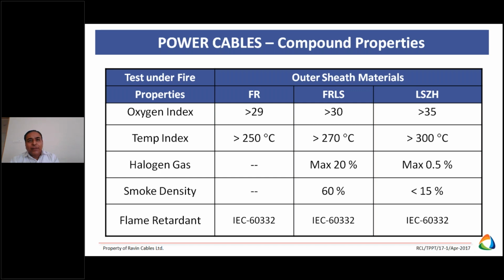Fourth condition, if the fire process starts, PVC burns and, by its properties, releases smoke. Smoke is what? Black color. It should be low so that people can again see the staircase or safe place where we can evacuate. These are the conditions required in flame retardant, low smoke. Again, this is the design parameter.